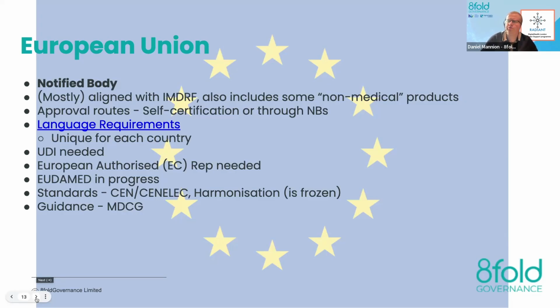For the EU, your approval, there's self-certification for Class 1 medical devices, or you're approved through a notified body. Each country of the EU has its own language requirements, and thankfully about 2 years ago, the European Commission put up a document that explained for each country what the language requirements are for your user interface and for your instructions for use. There's a link, if these slides can be shared afterwards, to that. Before that, you had to do it yourself. So you had to go to the German implementation of the European medical device regulation and say, what does it say about using German language versus English language, which was not a fun job that week. I did that.